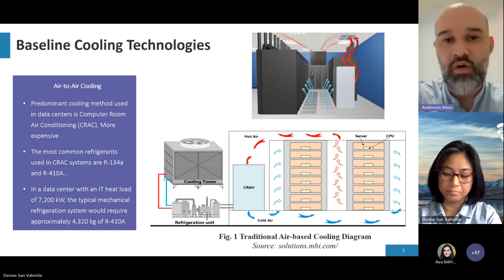If we take a typical data center with a load of 7,200 kilowatts of power, the cooling equipment would have roughly 4 metric tons of refrigerant inside. When you multiply that by the GWP of the refrigerant, and then by the quantity of data centers a country may have, you're easily talking about hundreds of thousands or even millions of CO2 equivalent stocked only in the data center cooling units.